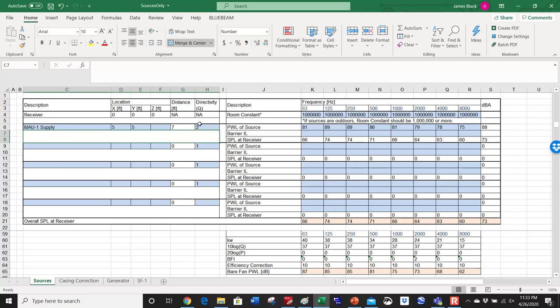So that's what this is. So it's sitting on a roof. So you have basically infinity, or we were saying room constant of a million. So this ends up giving the sound pressure level at a receiver for the sound power levels that we enter at the distance and the directivity and the room constant. So there's 76, let's change this to 10. I hope that will be 70. Yeah, so 70. And then it sums up all these sources here.